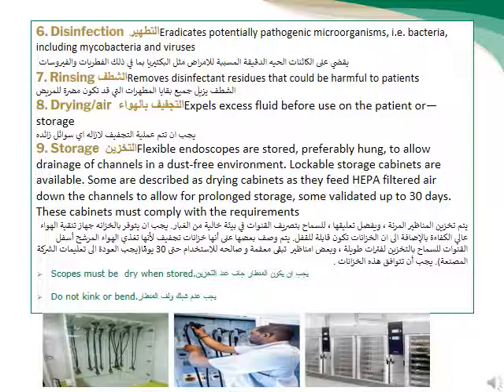Disinfection: eradicate potentially pathogenic microorganisms, for example bacteria including Mycobacteria, and viruses. Rinsing: removes disinfectant residue that could be harmful to the patient. Drying by air: expels excess fluid before use on the patient. Storage: flexible endoscopes are stored preferably hung to allow drying of channels, in a dust-free environment. Lockable storage cabinets are available, some described as drying cabinets, which feed HEPA-filtered air down the channels, allowing storage for up to 30 days.